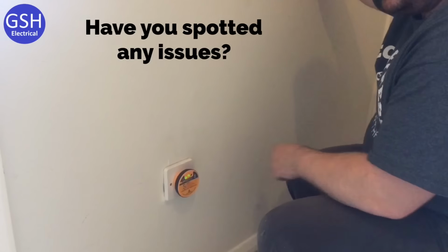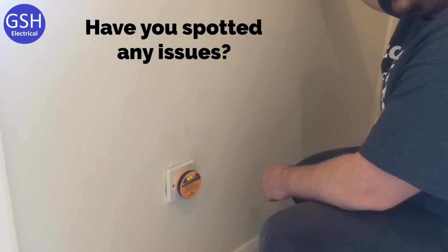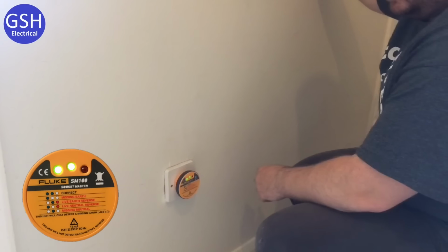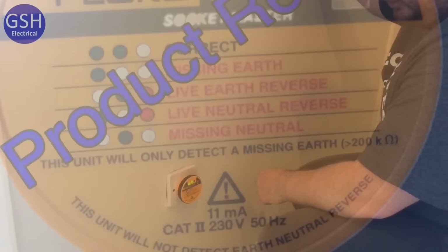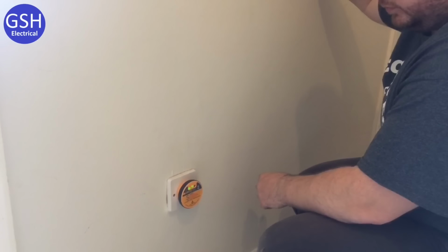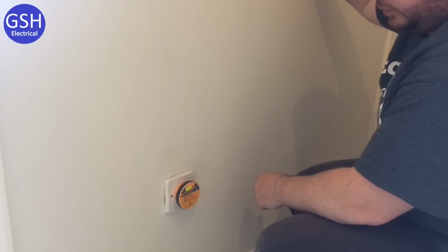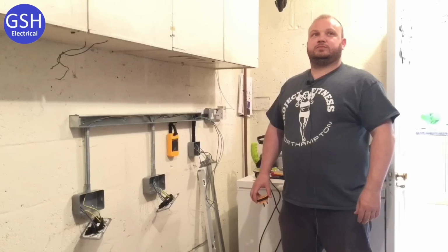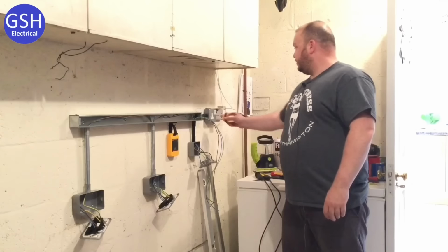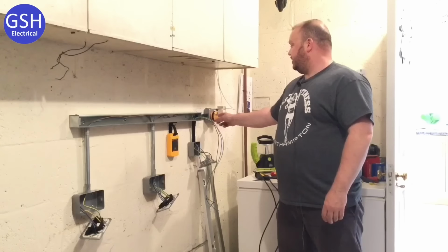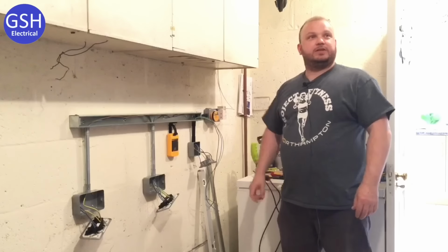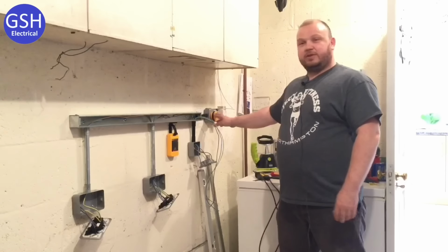So Mark has plugged his plug-in voltage indicator in the upstairs ring final circuit just to prove it works, and 2 green lights on this test to suggest it works. We're also going to prove the circuit downstairs using our GS38 test probes and proving unit, but we're going to use a plug-in voltage indicator first. So what are you going to do now with your plug-in voltage indicator, Mark? So what I'm going to do now is I'm going to plug this in, check that this socket is on and live. You've got 2 green lights? This is on live, it's taken 2 green lights.